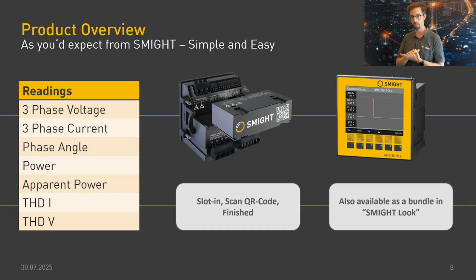So let's have a look at what we're measuring and how this works. The core measurements we're taking are 3-phase voltage, which is a difference from our normal standard setup, since our gateway normally takes just 1 voltage. If you're interested in 3-phase voltage, this is the best way to do it at the transformer level. We also measure the 3 current phases, the phase angle, power and apparent power, which is new since we weren't measuring power before.